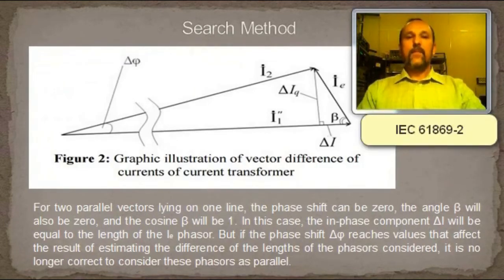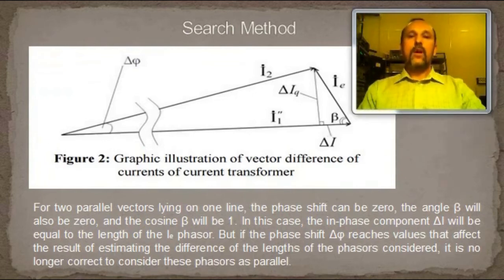International standard IEC 61869 part 2 has the Annex A, in which an explicative vector diagram is given to explain the determination of the ratio error. This annex illustrates the error triangle, which distinguishes two components of composite error, namely the in-phase component and the quadrature component of exciting current, which is composite error.